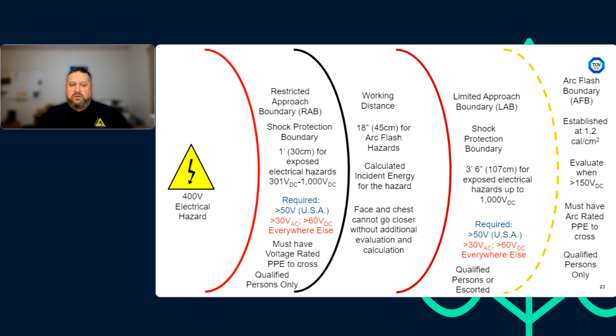Our working distance is where we calculate our incident energy, which we'll go into more detail on inside of a class. And then our restricted approach boundary: if we cross this boundary, we basically assume that because we're working with our hands or whatever, we're getting close enough that we'll inadvertently come into contact with that energized conductor. So to cross that restricted approach boundary, we have to have rubber gloves and leather protectors. So these boundaries each have their own special purpose. They're important to understand, and that's one of the biggest things to walk away with when learning about the high energies of battery systems.